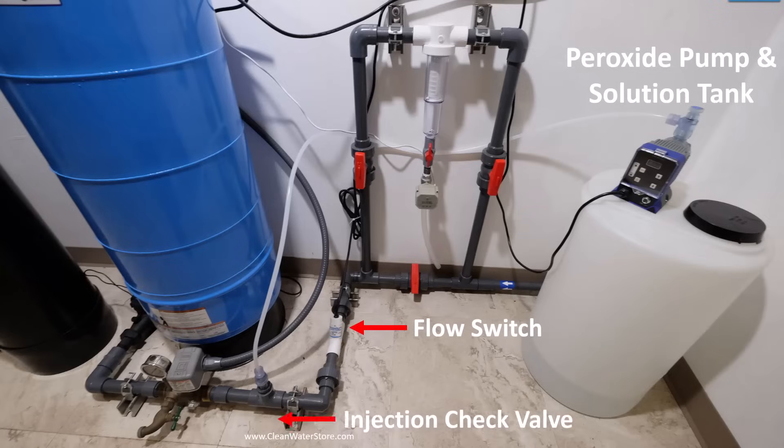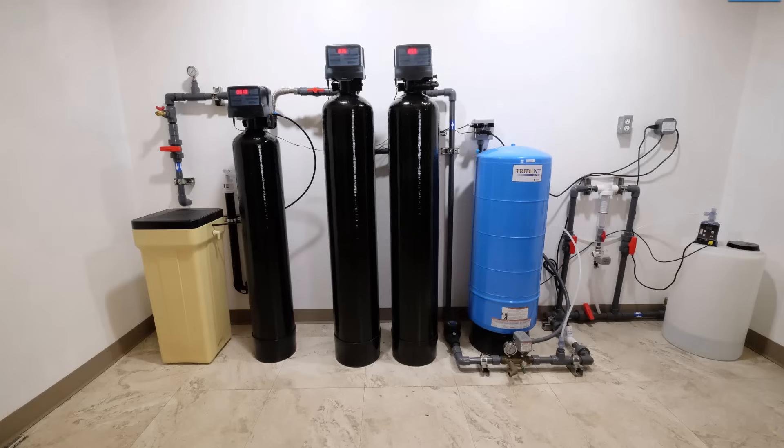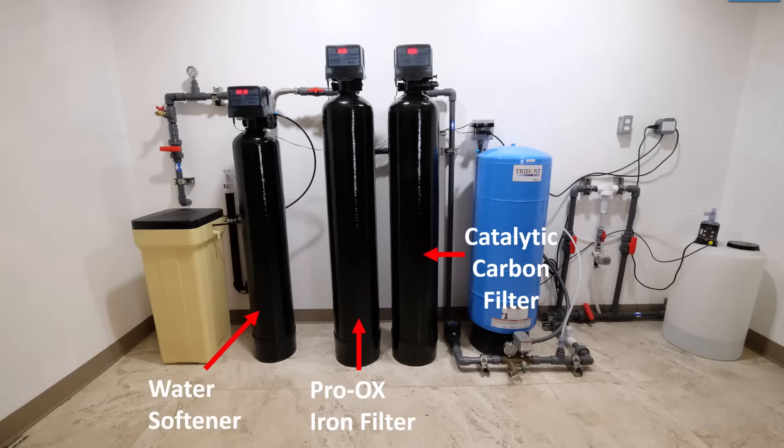Here's a typical system set up to inject peroxide before the pressure tank. In this case, the peroxide pump is turned on and off by an optional flow switch. In some cases, if the water has a lot of iron or it's very hard water, folks will have a Pro-OX iron filter and a water softener after the catalytic carbon filter.